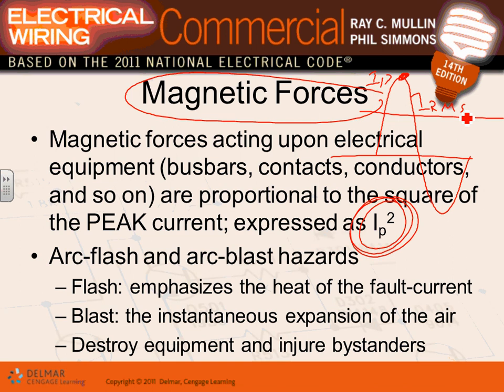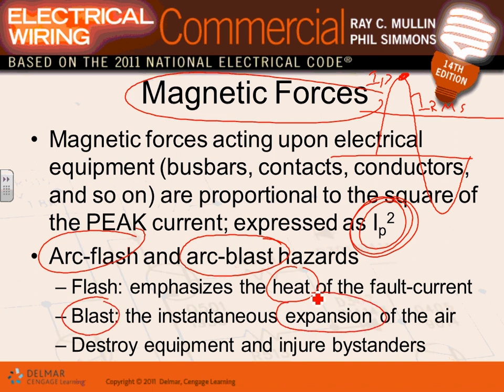Arc flash and arc blast. With this, guys, come the two terms that we use. Arc flash is your heat. That's how much, when you have an arc flash condition, typically it's a high impedance short circuit, you have more energy released that's going to burn the equipment. Blast is the expansion, the magnetic force will get you an expansion of the heat. The heat will start expanding at a higher rate, and with it take all that melted copper and throw it right into the electrician's chest. Bomb. You're talking about a bomb condition, right?